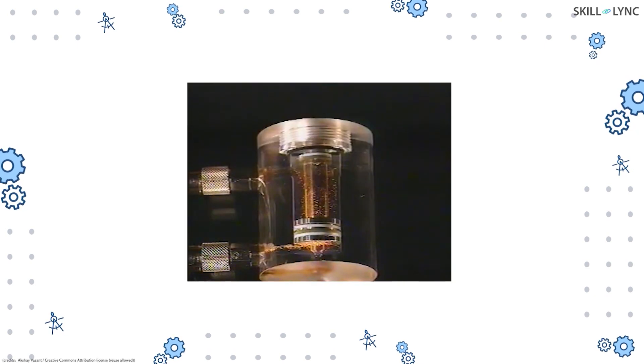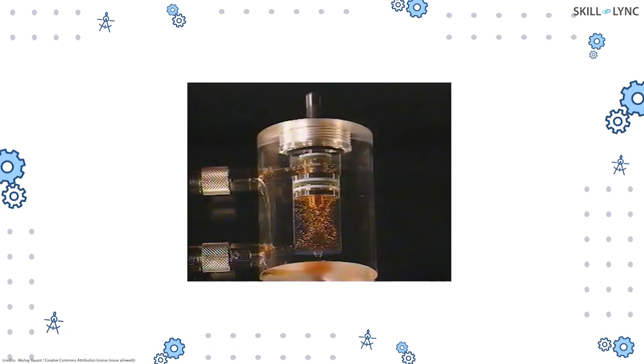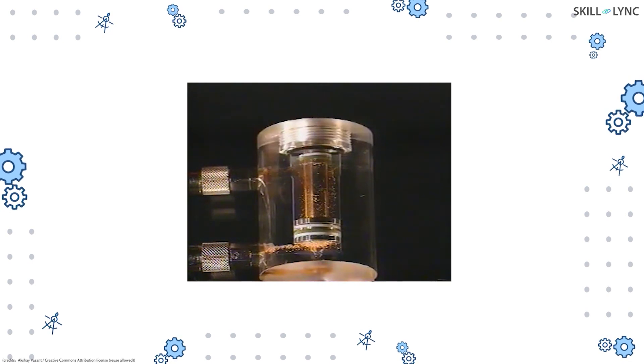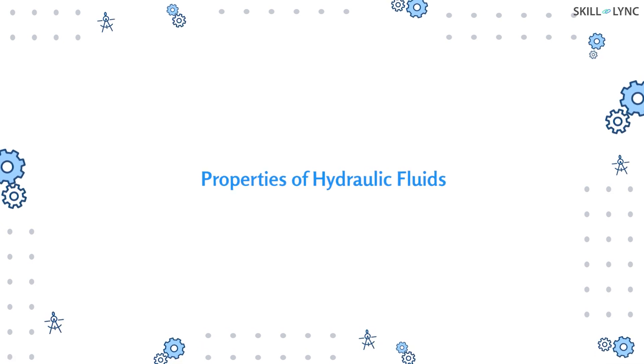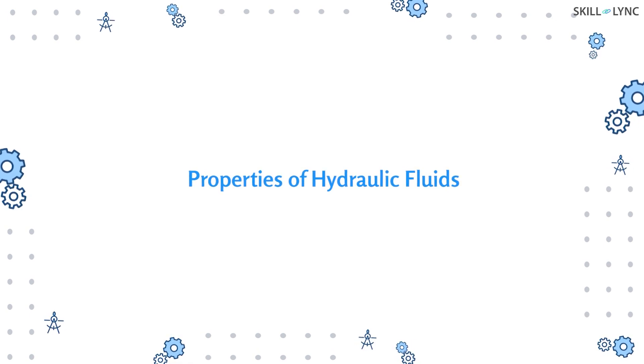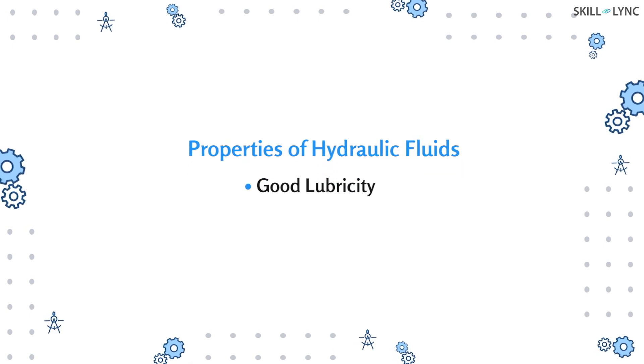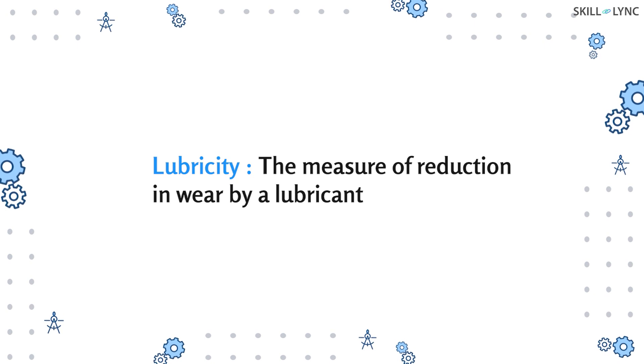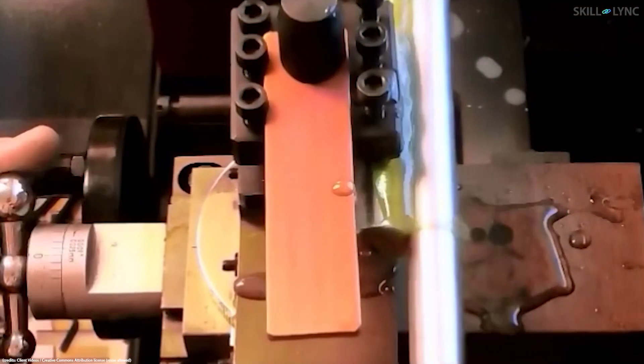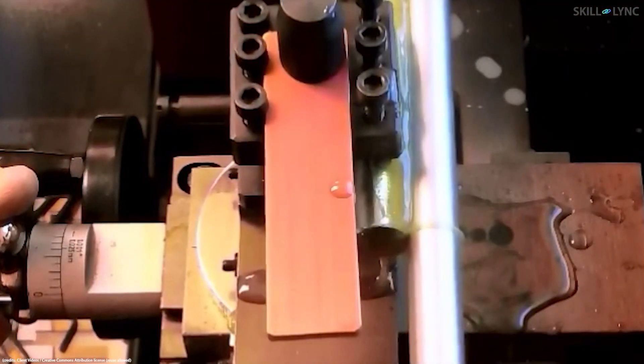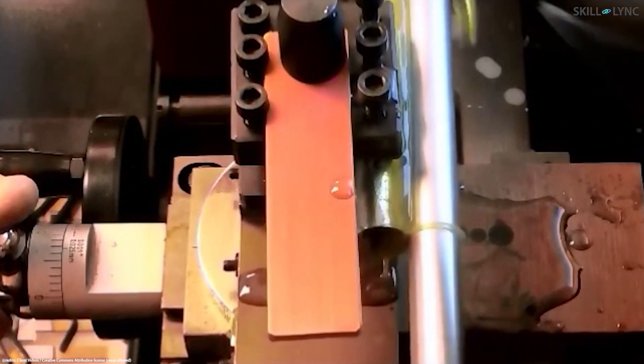The selection of hydraulic fluid is dependent on the requirements of the power system. Nonetheless, the hydraulic fluid must possess some properties to be used in a hydraulic power system. Let's discuss some of these properties. First of all, the hydraulic fluid must have good lubricity. This is because if the surfaces of various components come in contact, it may cause wear and damage to the system. Thus a hydraulic fluid having good lubricity separates and lubricates the components effectively.